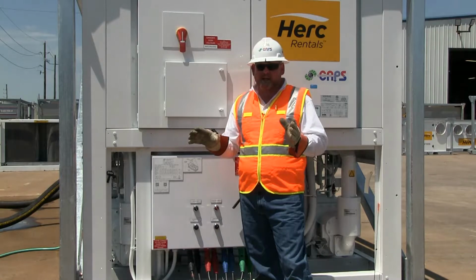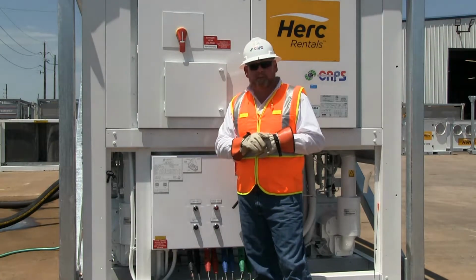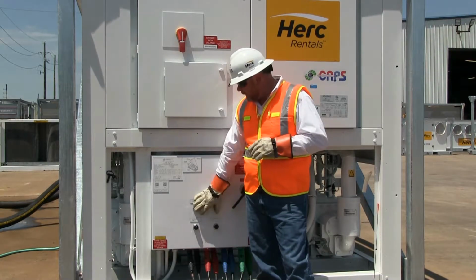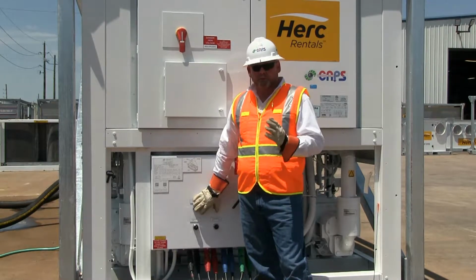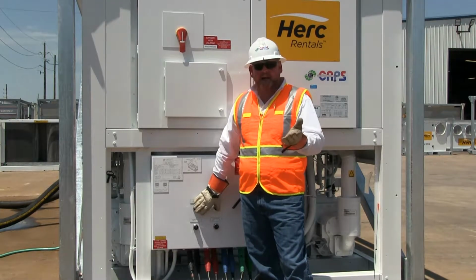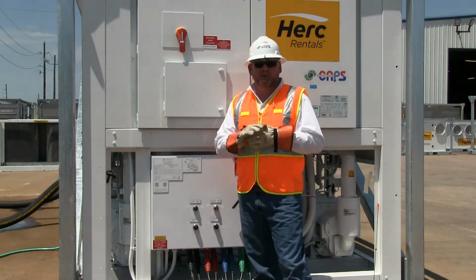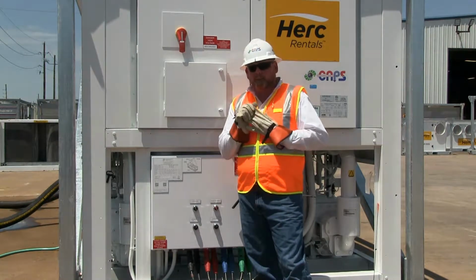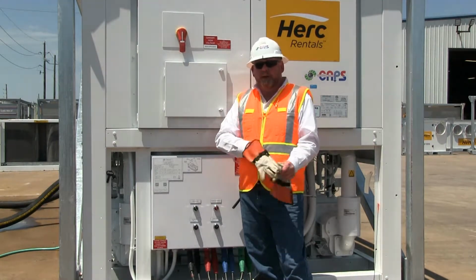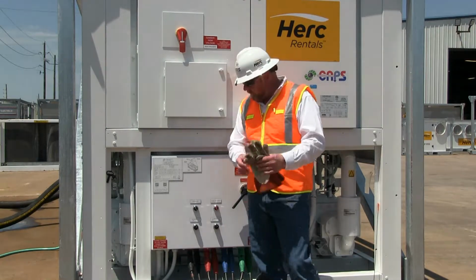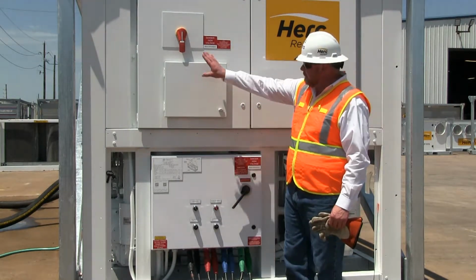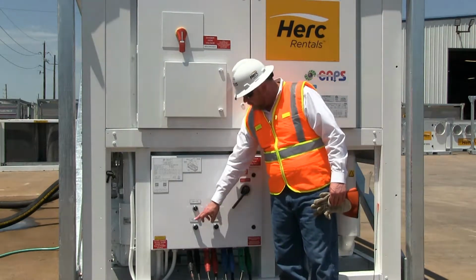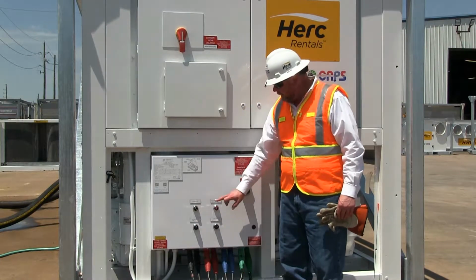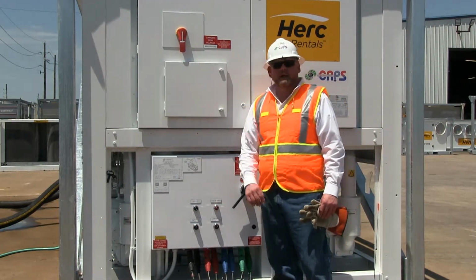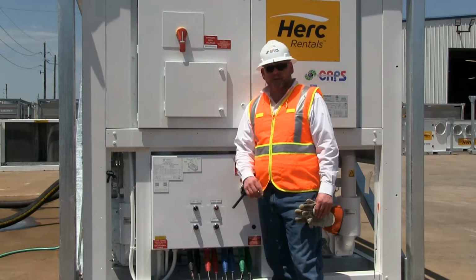We're fully pressurized at a standing pressure of about 50 psi. We've had our power on for about an hour and a half, so our crankcase heater timer is timed out. The compressors are now safe to start, so we don't need our PPE hot gloves anymore. From now, we're going to go through the control panel. We've got our pump currently on, main power's on, our pump's running, master switch is on, power's on, phase is correct. Now we're ready to go through the control panel and set the chiller up into permanent operation.